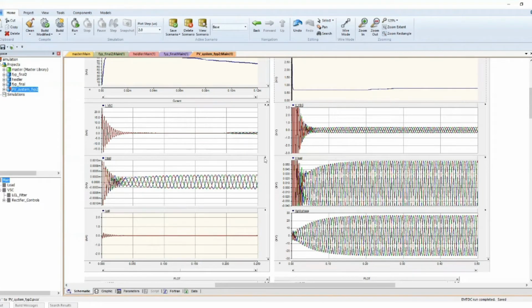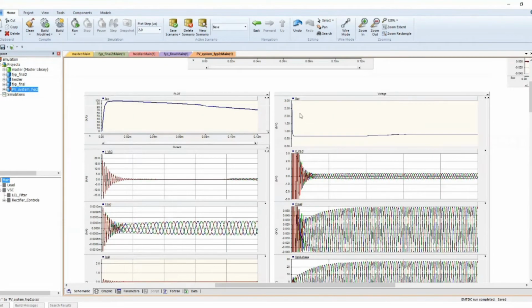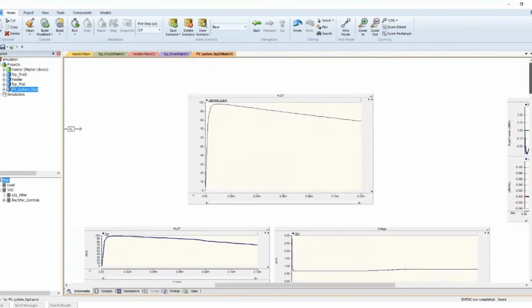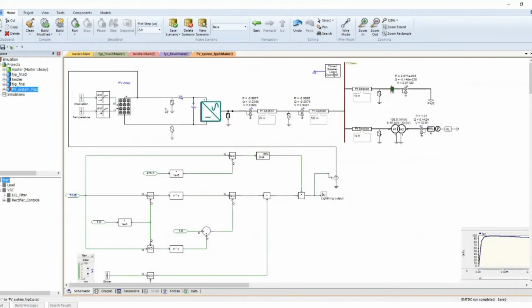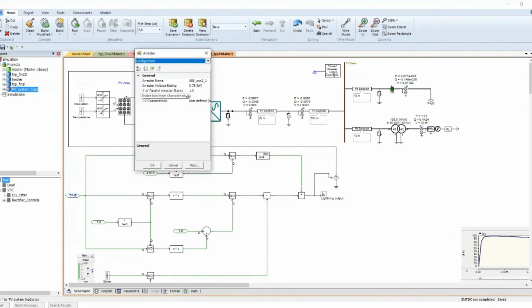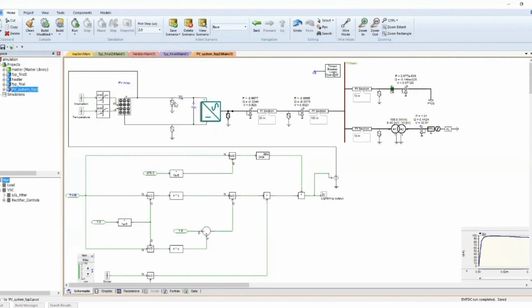We can see that when the lightning strikes the system, there will be an overvoltage and distortion component in the PV system. Here is the circuit of the PV system with the installation of surge arrestors at the recommended locations. The surge arrestor at the DC side has a voltage rating of 0.78 kilovolt. The surge arrestor must be designed through its IV characteristic. With this designed surge arrestor, it can clamp the overvoltage that occurs in the PV system when lightning strikes the system.